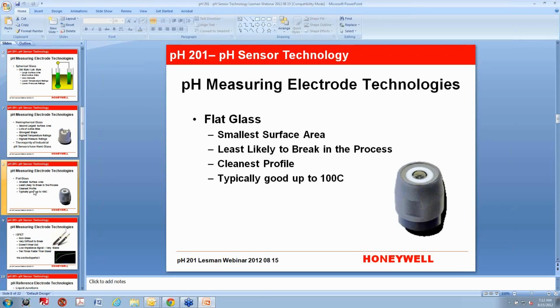It has a flush profile with the liquid junction and the body of the sensor. I would also consider it the cleanest profile because it doesn't have anything sticking out that your process may tend to build up on. So it's not going to get coated up usually as quick as a hemisphere or a spherical glass. These are typically good only up to 100 degrees C. Some of our hemispheres go up to 140 C. In fact, in a different body style, we can actually do 150 C, which is the highest temperature rating in the industry. But anyway, flat glass is good up to about 100 degrees C.